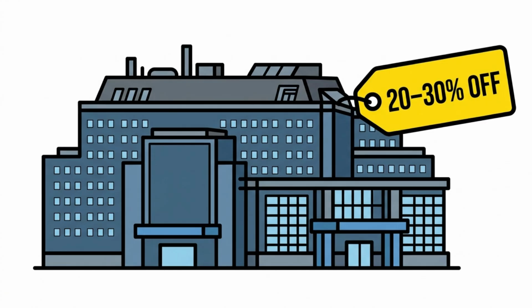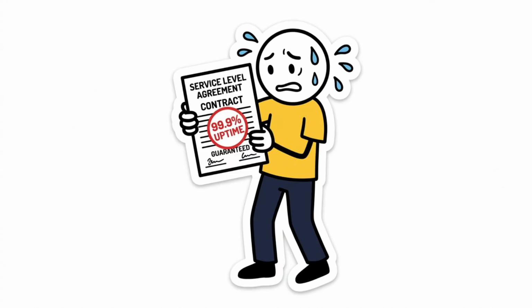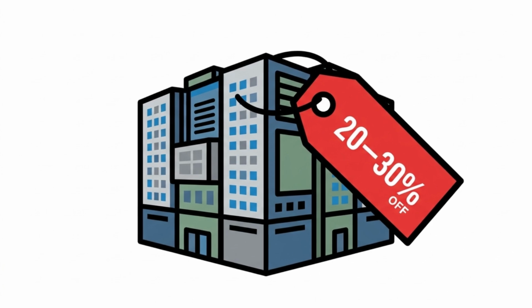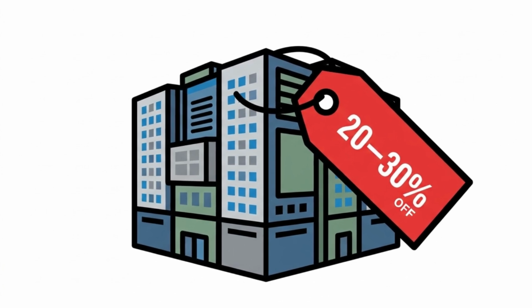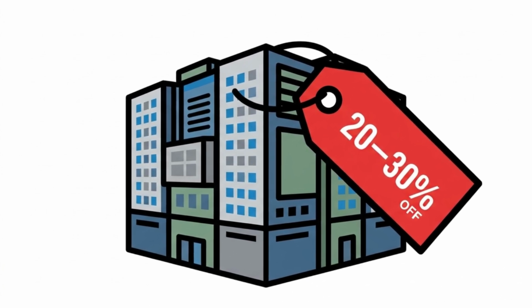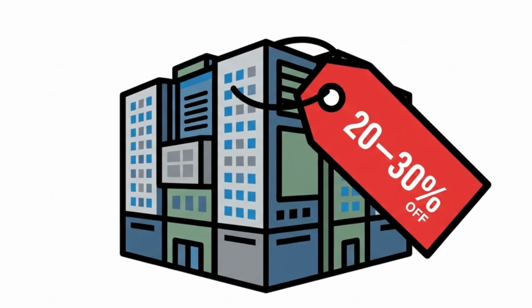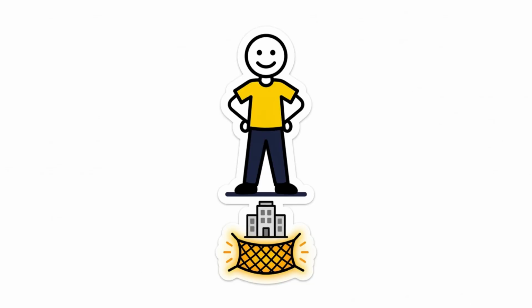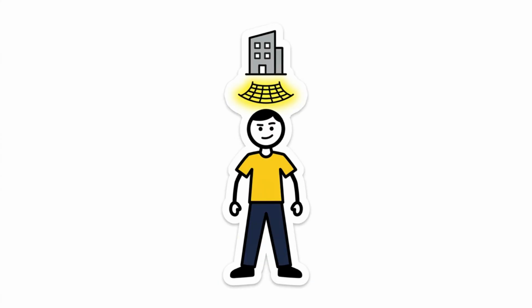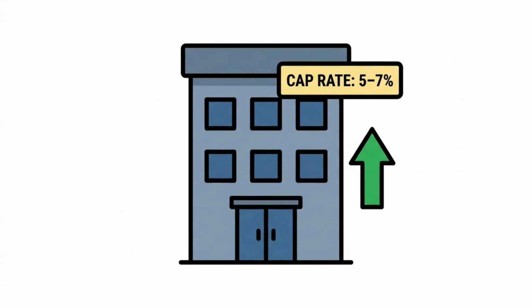Layer 5, and this one surprises people: the biggest tenants often pay the least per kilowatt. Hyperscale clients signing 10 to 15-year leases for 50 plus megawatts negotiate steep volume discounts, sometimes 20 to 30% below market rate. Read that again. The company with the deepest pockets pays the smallest unit price because their long-term lease de-risks the entire facility for the lender who financed it in the first place. Stability, not size, is what gets rewarded.